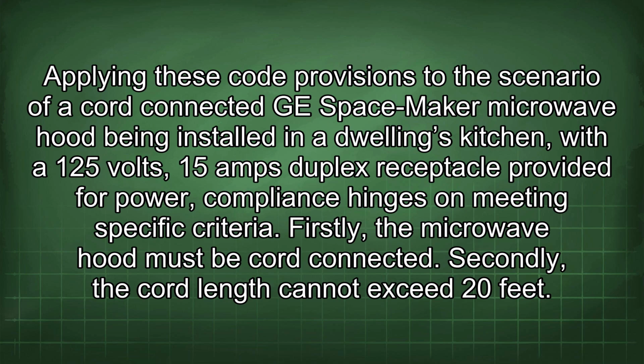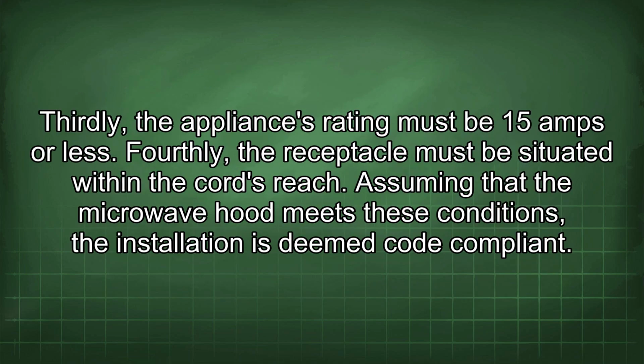Firstly, the microwave hood must be cord-connected. Secondly, the cord length cannot exceed 20 feet. Thirdly, the appliance's rating must be 15 amps or less. Fourthly, the receptacle must be situated within the cord's reach. Assuming that the microwave hood meets these conditions, the installation is deemed code compliant.